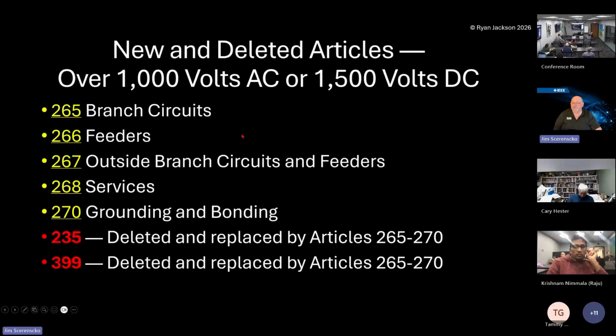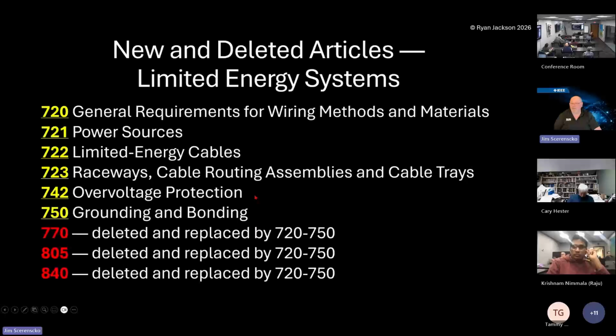So some of the new articles: 265 for branch circuits over 1,000 volts, 1,500 volts DC, all of these branch circuits, feeders, outside branch circuit services, grounding and bonding. And then of course 235 was deleted and replaced with 265 through 270, and 399 was deleted and replaced by 265 through 270. The limited energy systems that came out. I mean, we're putting in more limited energy, low voltage, than we are high voltage anymore, or just as much. It's becoming a bigger and bigger industry every time you turn around. So these are the new articles that you see, and what was deleted and why it was deleted.